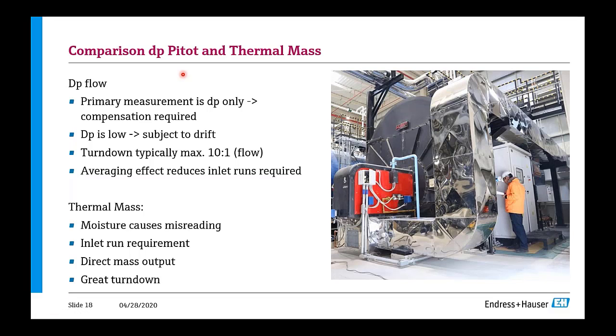So if you compare the technologies that are most common here, we have an application, this is a fire tube boiler, okay, that's a small one, but also here you see a rectangular duct of combustion air being used, and here you see this thermal mass flow meter, and there you could see also, maybe in other applications, a Pitot tube. So the mass flow meter has the benefit that you get the mass output directly, you've got a great turn down, but moisture can cause a misreading, that's an issue, and you have a certain inlet run requirement. Of course, with the insertion, you can't install a flow conditioner here very easily.